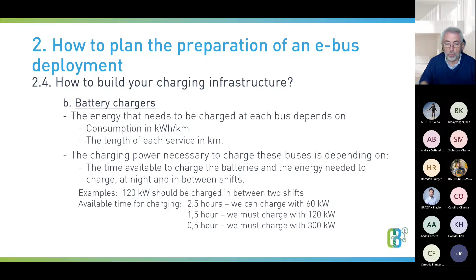Some examples: if I need to charge 120 kilowatts between shifts and have 2.5 hours to do it, a 60 kilowatt charger works easily. With only 1.5 hours, I need a 120 kilowatt charger. In half an hour, I'd need a 300 kilowatt charger. So the advice is: don't use a larger charging capacity than necessary if there's enough time to charge with a lower one. It's even better for the lifetime of your batteries.